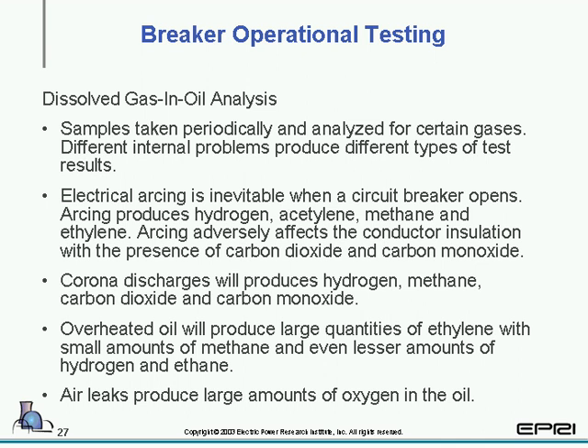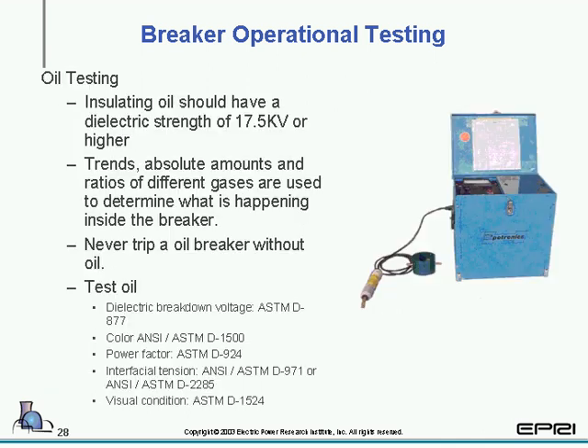Some of the other, less known or less used, are oil breakers, and so we're just going to kind of look at those because they're a little outside the box of our particular 15 kV and below breakers. And again, you want to take a sample of the oil and have it sent out and looked at, because certain types of gases indicate certain types of problems. You can also do insulation resistance testing, and we have a couple of values for what would be a minimum; 17.5 kV or higher is what you would expect to see. And if you're doing these types of tests, at the bottom we have a couple of ANSI colors and standards that can be followed.